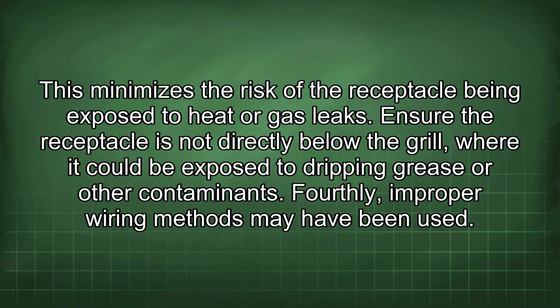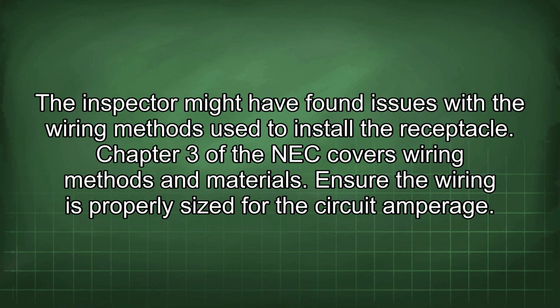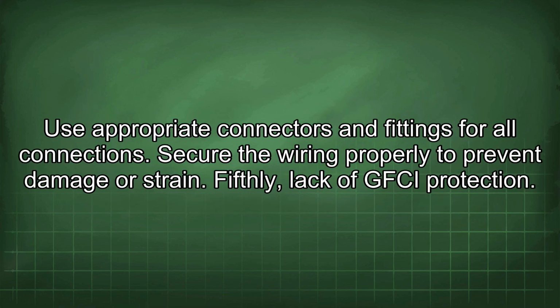Fourthly, improper wiring methods may have been used. The inspector might have found issues with the wiring methods used to install the receptacle. Chapter 3 of the NEC covers wiring methods and materials. Ensure the wiring is properly sized for the circuit amperage. Use appropriate connectors and fittings for all connections. Secure the wiring properly to prevent damage or strain.